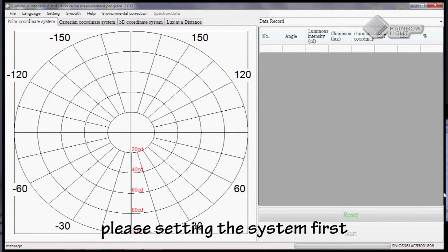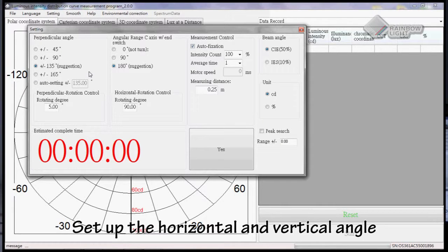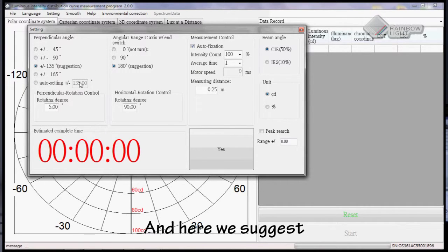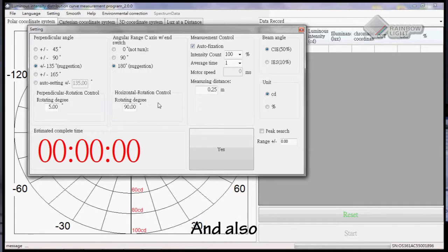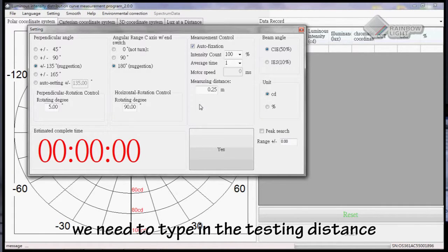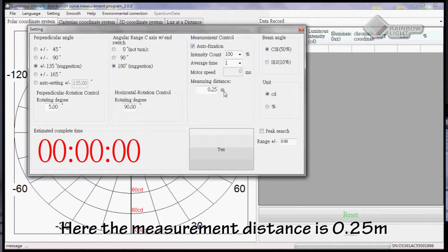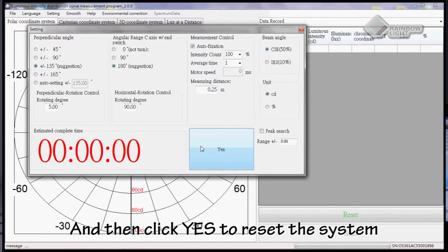Before doing the measurement, please set up the system first. Set up the horizontal and vertical angle which makes the light rotate automatically. Here we suggest you to use this number and this number. We also need to type in the testing distance. Here the measuring distance is 0.25 meters. Then click yes to reset the system.